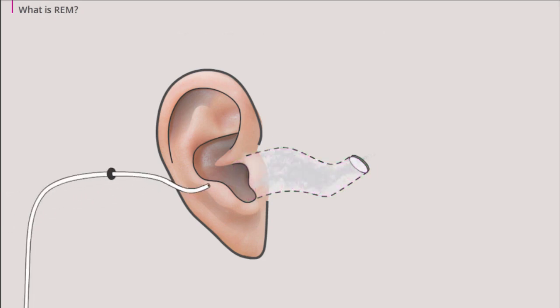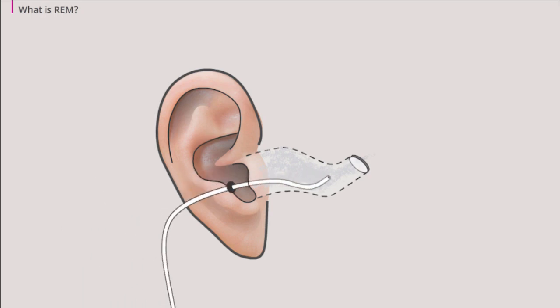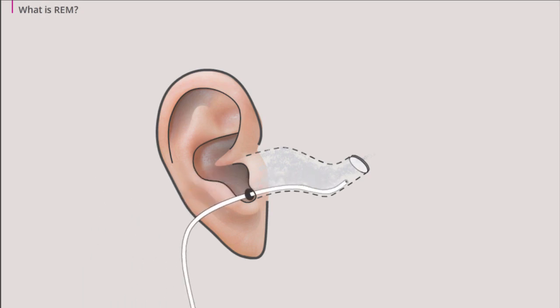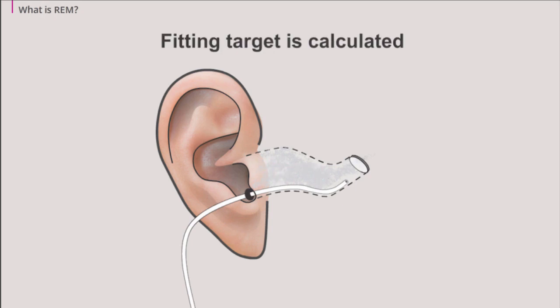When performing a REM, you insert a small probe tube into the client's ear. While playing a test signal, the sound level in each ear is measured. First, the real ear measurement is done without a hearing aid. With this measurement, a fitting target is calculated.